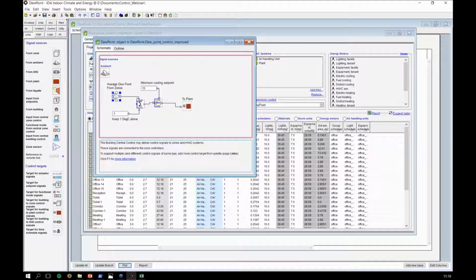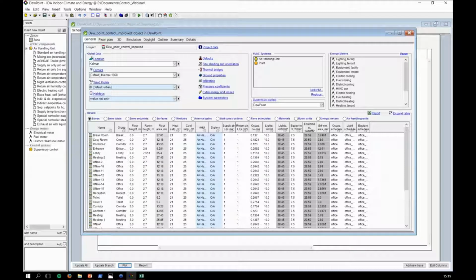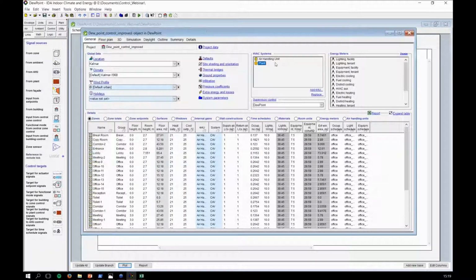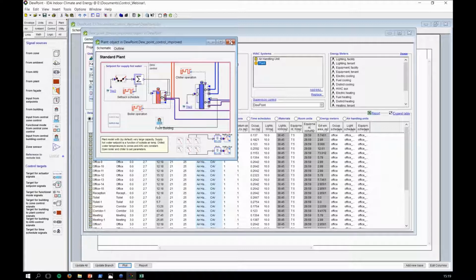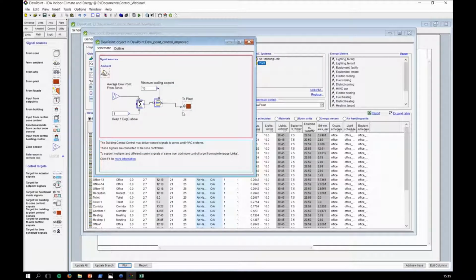And I'm making sure that I don't go below 15. So I'm using the maximum of that signal and whatever 15 is. So when this temperature dew point control goes below 15, my output here will be 15. So this is another way of doing dew point temperature control. And the plant, nothing changes in the plant, it's the same. But this ensures that since I'm not dependent on the mass flow rate and the humidity sensor, this is more stable. Although it's probably less realistic to have a humidity sensor for every zone. But from a simulation perspective, it's more stable.